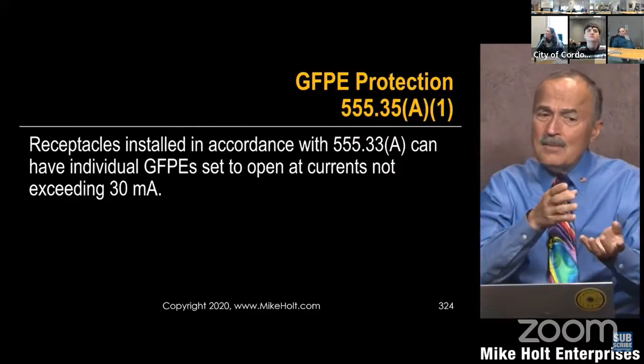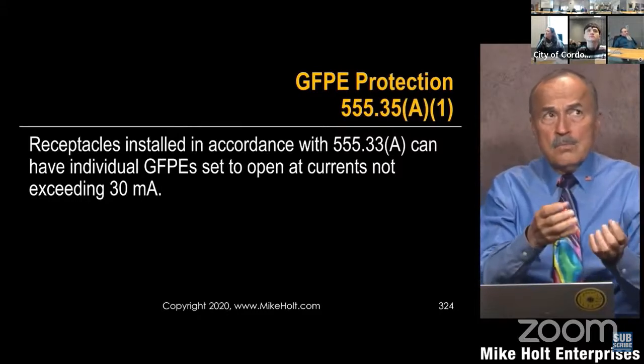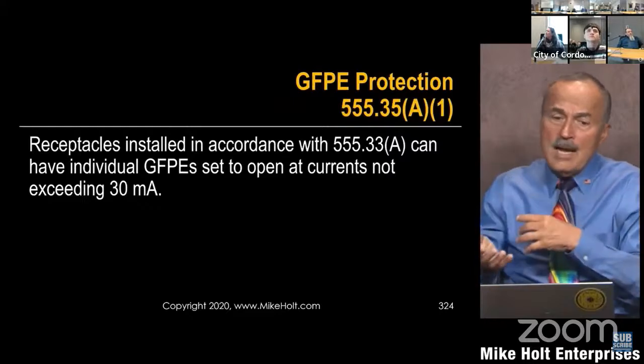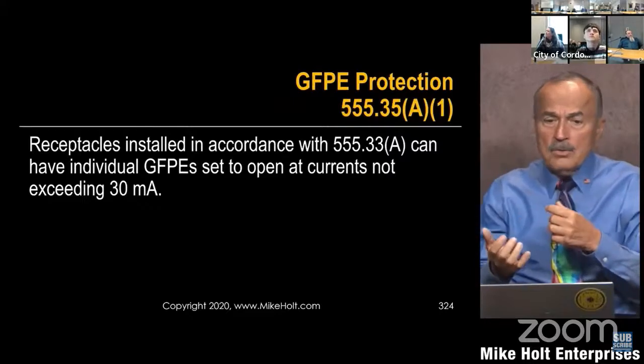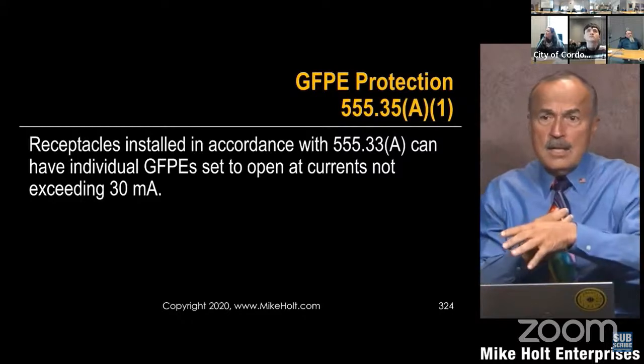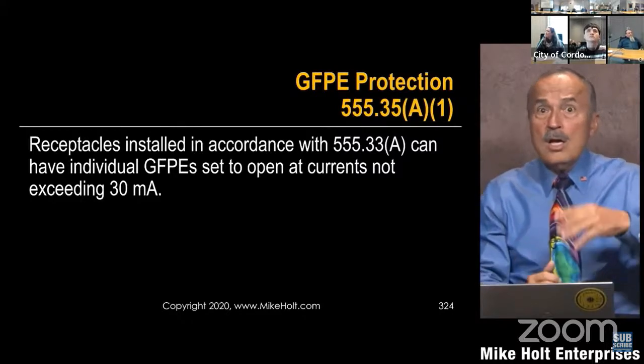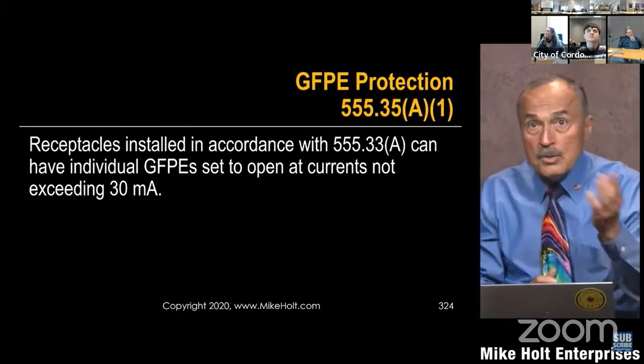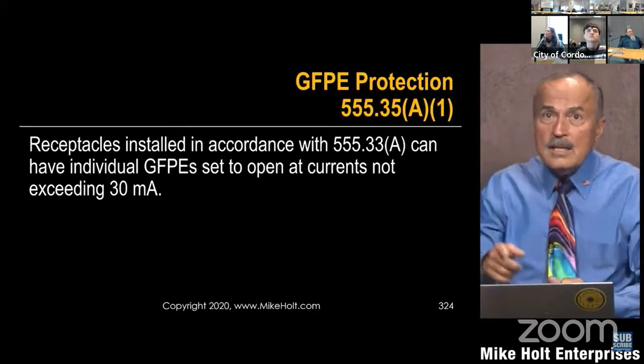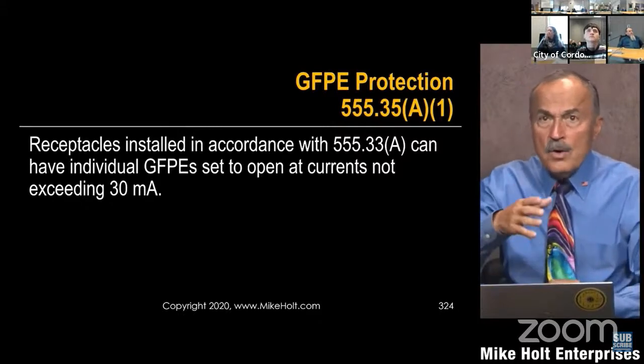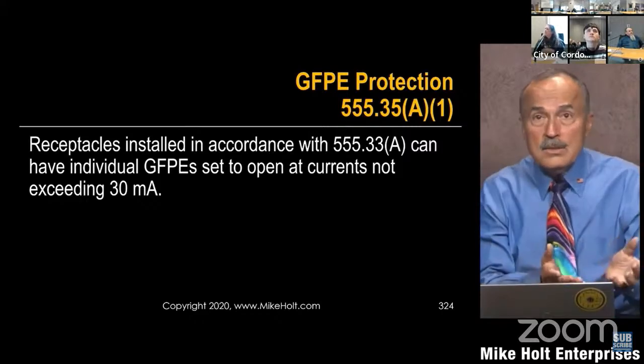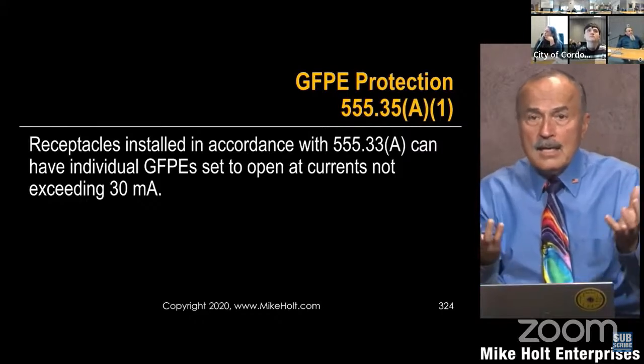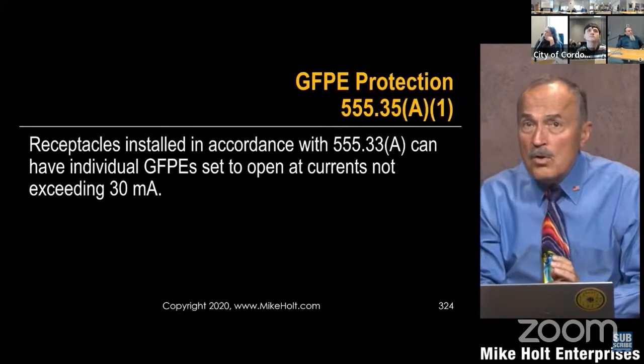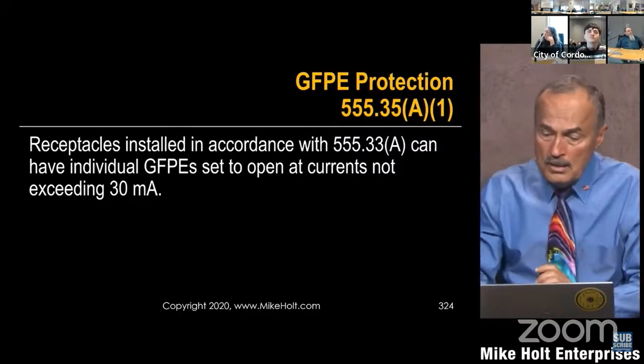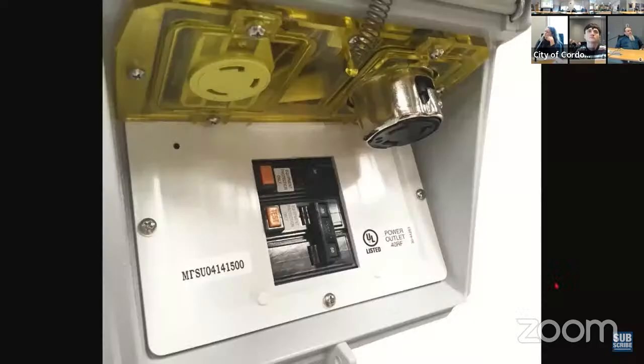And if there's any kind of failure in your boat, the boat is in the water and it has a shaft and a rudder and propellers, and there's a fault inside the electrical system, and you lost the effective ground fault current path coming to the boat itself, well, the ground fault current will be limited to the water current path. It's not going to be a fault, but it will go more than 30 milliamperes, and it will trip that ground fault protection equipment, right?